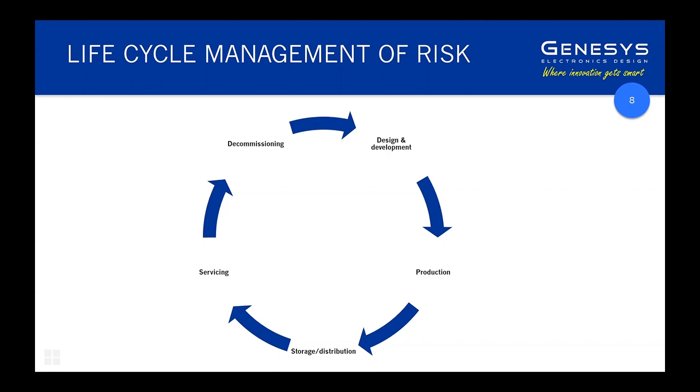If you're doing software, I would expect to see a software risk analysis that's required as part of the standard. Design FMEAs, process FMEAs. You might see some human factors FMEAs in there, but there's a whole bunch of different types of methodologies for risk analysis. For example, fault tree analysis and HAZOPs and things like that.